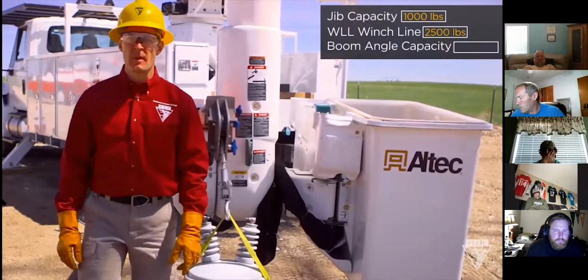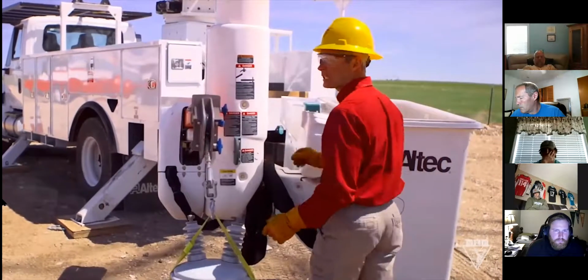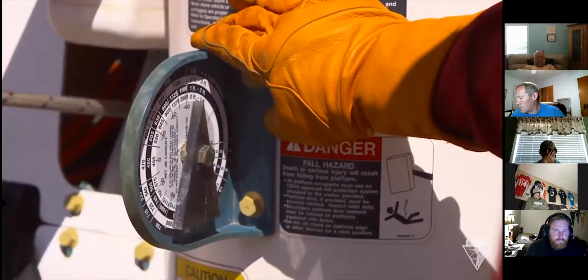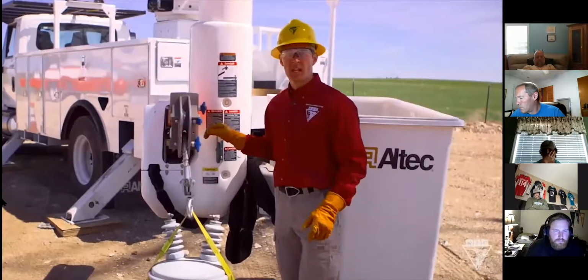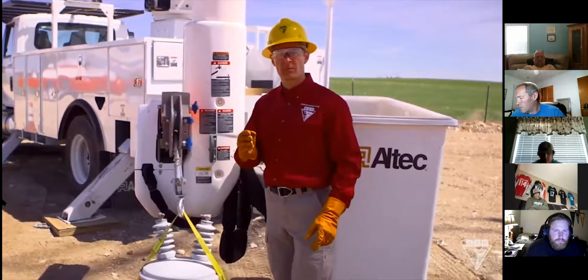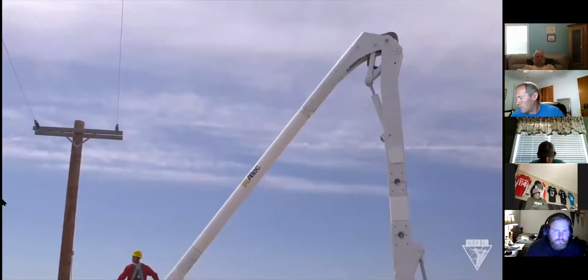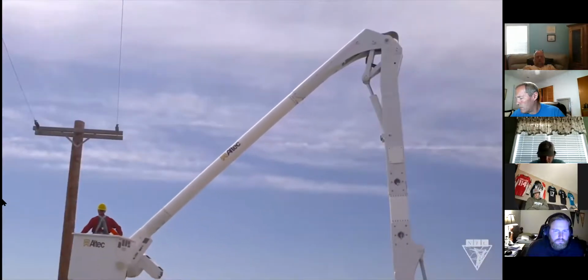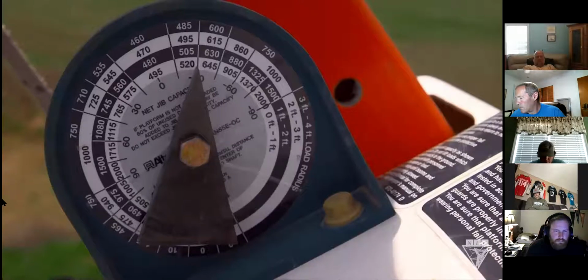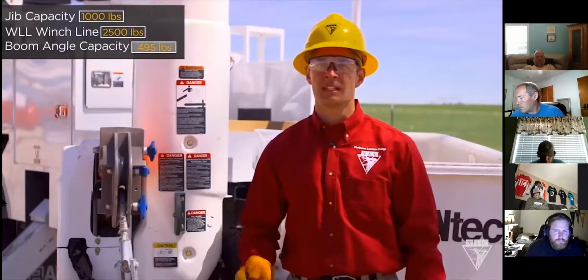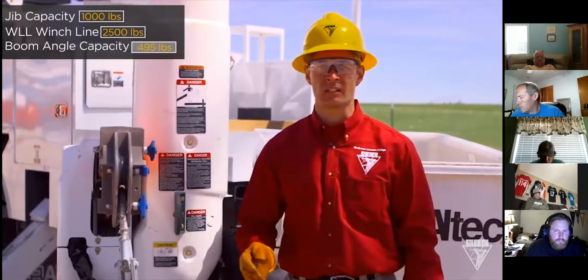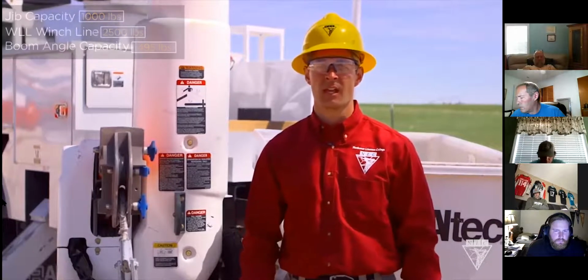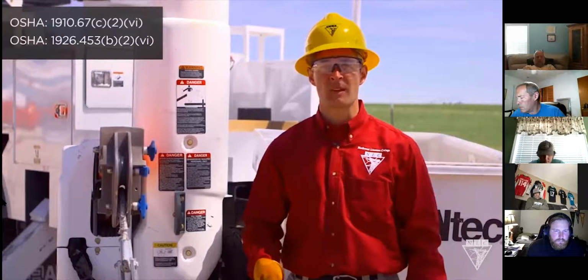Let's take a look at the boom angle indicator. Keep in mind, as the boom angle changes, the jib capacity will change as well. NLC recommends that you do a pre-run with the bucket before lifting your load. I did this earlier and found that my weakest angle was at -30 degrees. And when you factor in the 2.5-foot extension, that puts us at 495 pounds. So my weakest link is the boom. Keep in mind that these numbers can vary greatly depending on the truck you're using. And to comply with OSHA, you have to always make sure you're working within your load limits.